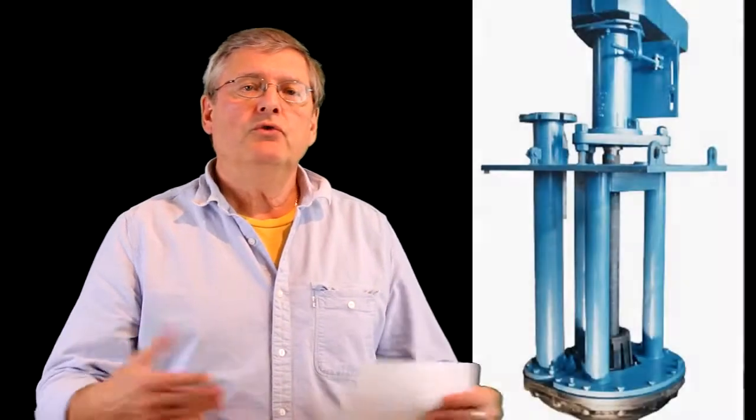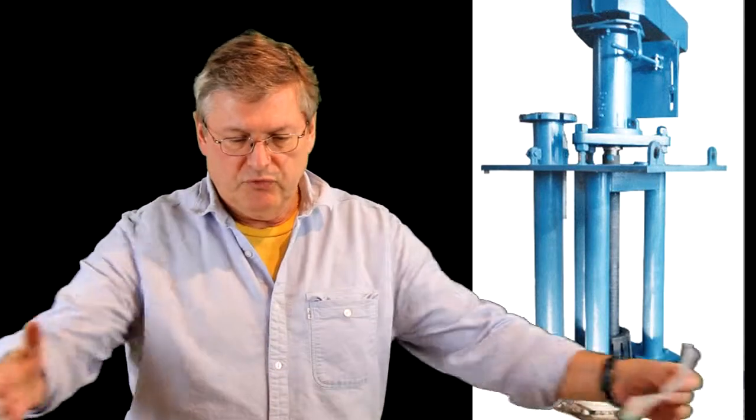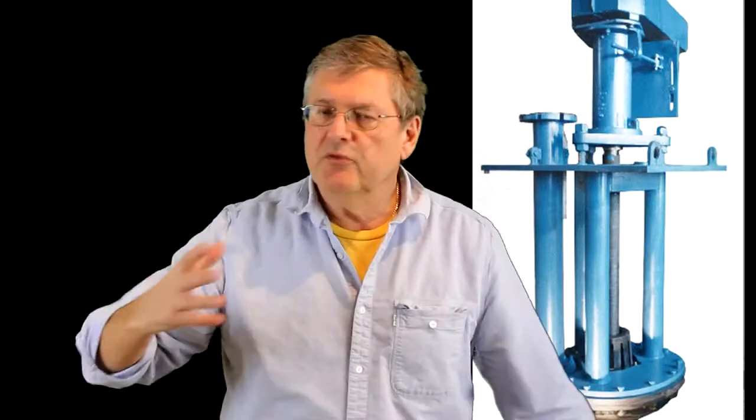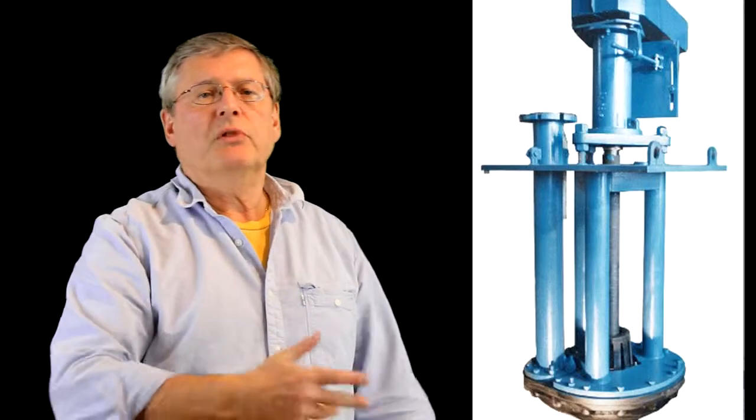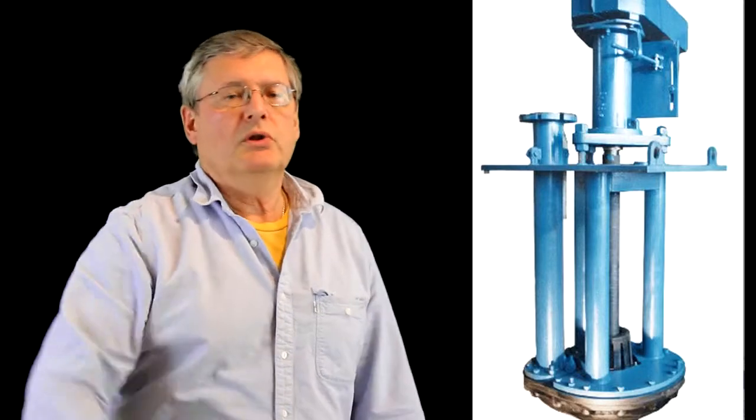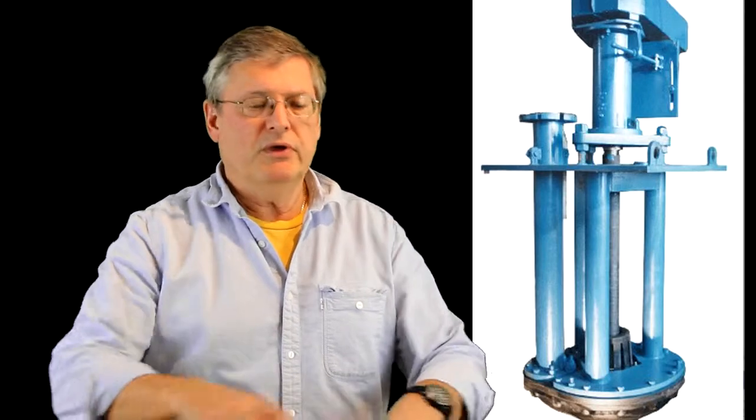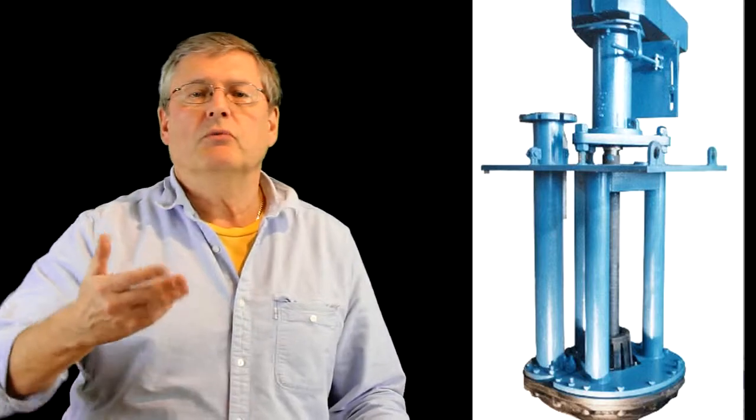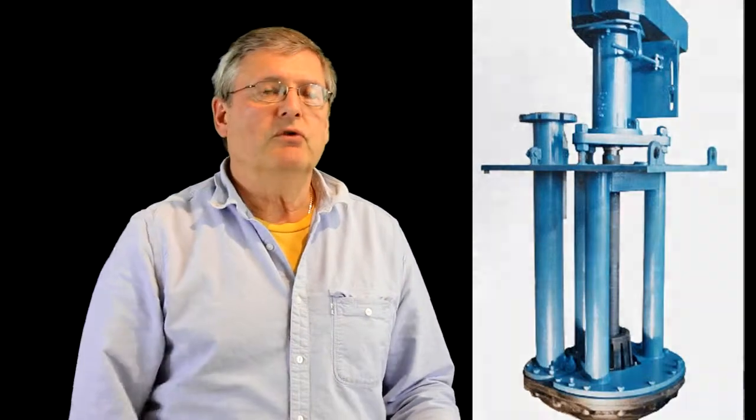This is a vertical cantilever pump. It's used in industry for sumps. These are pits that are a certain size, four foot by four foot. The pump is in the bottom, it's pumping out whatever mix is coming from the trenches of this plant to a holding tank somewhere for treatment. It's a very robust pump. The pump itself is submerged and the motor is at the top, dry and easily changed.